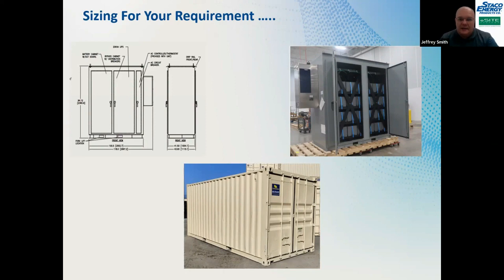Especially on the right-hand side, those are batteries. We get many applications where the customer says we don't have room in our facility, but if you put batteries outside, they won't last. They need to be in an environment around 77 degrees Fahrenheit constantly. Some say that's just an average, but if it's 30 degrees one day and 92 the next, averaging to 77 doesn't work. We have to keep it constant, plus or minus a few degrees, to make sure those batteries will be there when you need them.